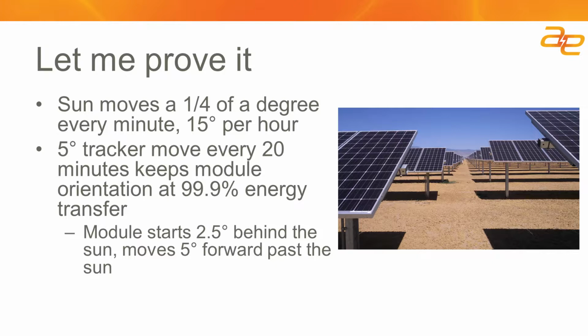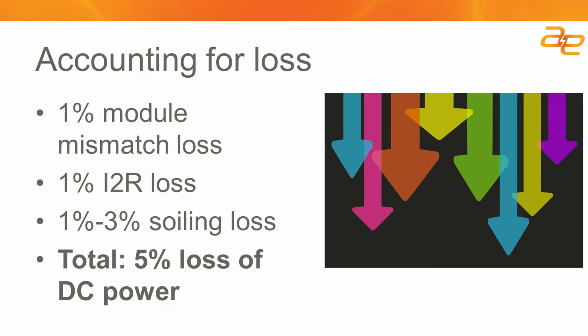20 minutes is less than the frequency that most trackers move. Most of them move every 5 to 10 minutes from my experience. So if you look at the losses in the system overall, if you have 6 megawatts of DC installed, there's probably about a 1% loss due to module mismatch. There's about a 1% loss just from the conductors carrying the current. There's resistive losses in the collection of energy. And then 1 to 3% is fairly typical for the amount of dirt and accumulation, the soiling losses you have on the modules. So a 5% overall loss in DC power is not uncommon.